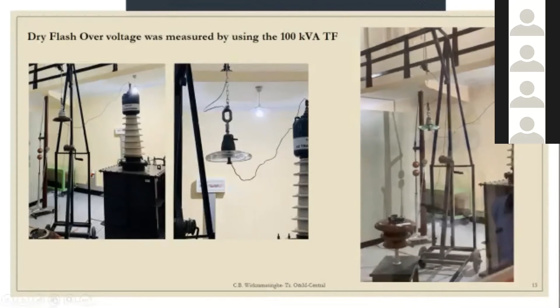That was a flashing over of an insulator. And then I calculated the leakage current at the wet condition also, similar to before, and the flashover voltage at the wet condition also. Now I have my laboratory results, and I have tabulated them. This is the oscilloscope voltage graph kV value, and from V equals IR, I was able to calculate the leakage current. It's in the microampere range. For the flashover voltage, I tested flashover 3 times and got the average value here. This is the dry condition and this is the wet condition.